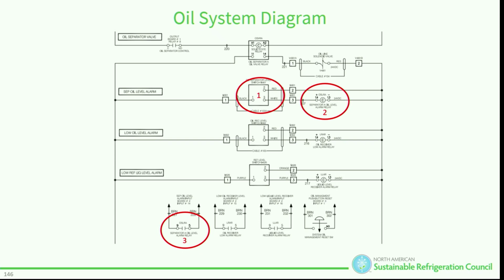If you've got a green light and you open up your flex, when you troubleshoot this circuit, you have to have your separator flex combiner open, because there's a separator high in there. If it doesn't turn on when that light turns green, then you're not making your input, or you've got a bad board input. It's either going to be bad contact on that OSLAR, or it's going to be bad input. If it's the contact on the OSLAR, you've got a spare one next to it, move it over. Save yourself some time. That's going to start our flex combiner, which is going to start pulsing our relay output board on our 8RO board, which is going to turn on our solid state relay and start pulsing our solenoid.